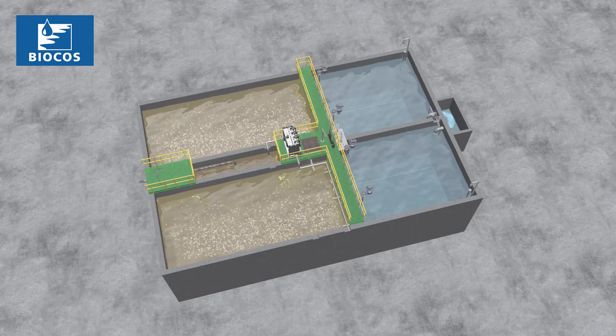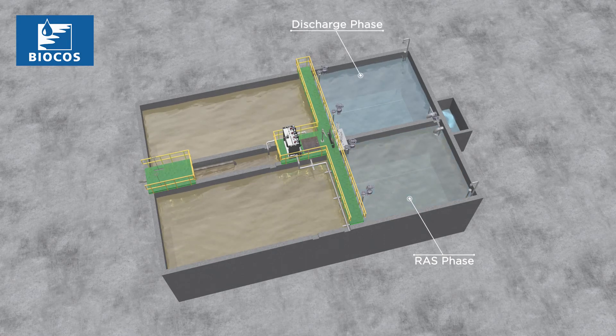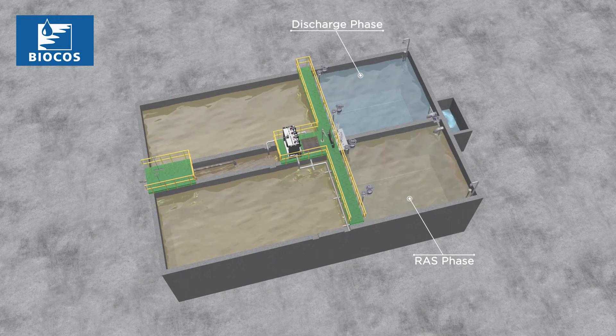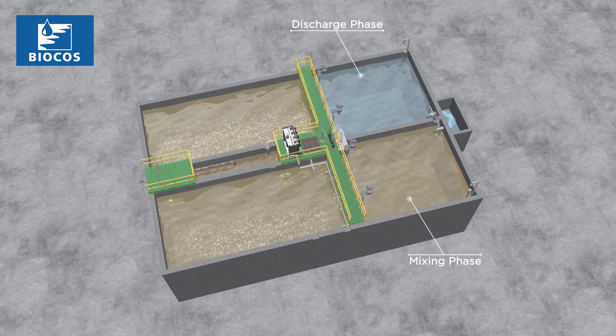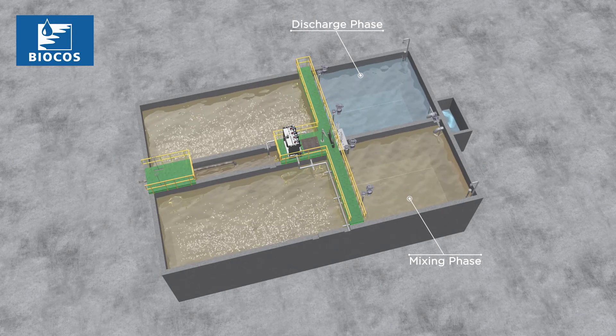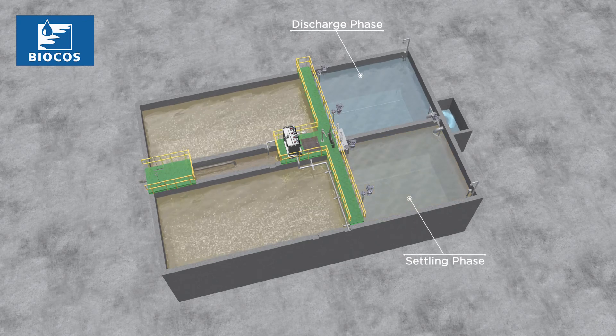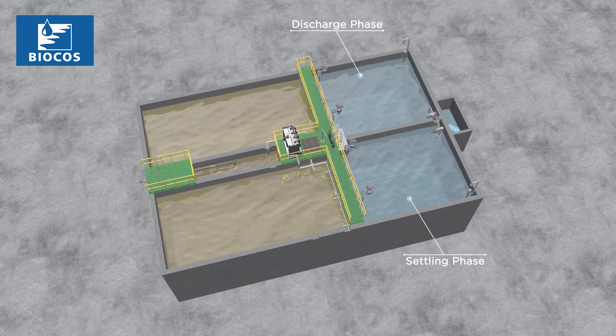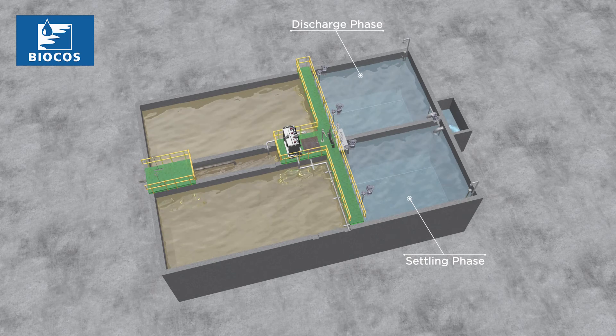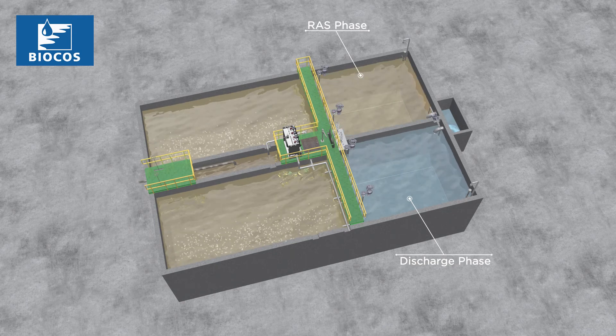The BioCos process is designed to be operated at preset time-controlled process cycles. The typical cycle duration is around 1.5 hours. Each cycle is divided into an RAS phase of 8 to 15 minutes, a mix phase of 2 to 3 minutes, a sedimentation phase of 27 to 35 minutes, and a discharge phase of 45 minutes. The preset cycle schedule may vary on a seasonal basis, but usually not on a daily basis, mainly depending on the kinetic rates, sludge properties, and the required sludge inventory.